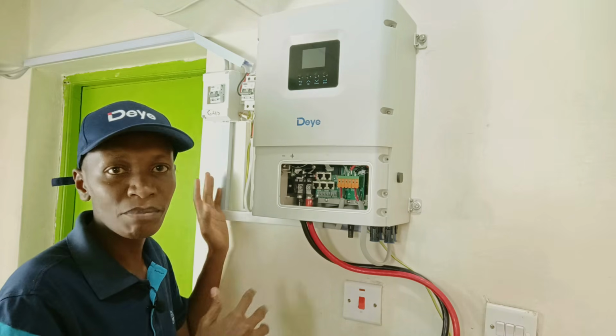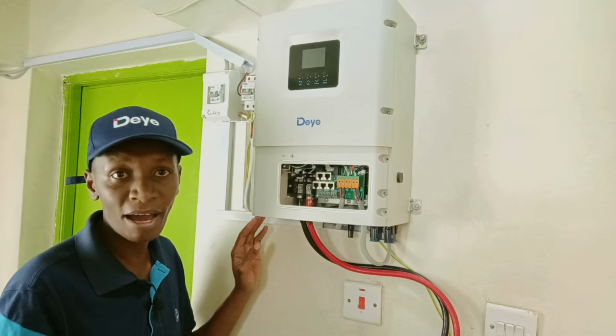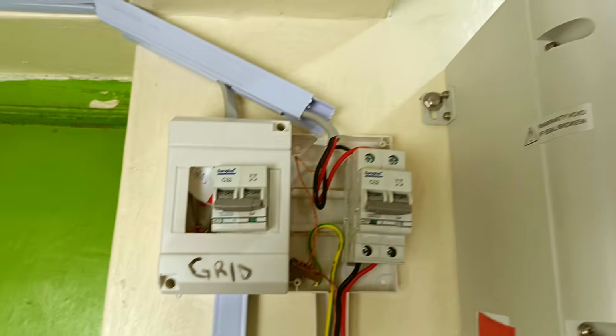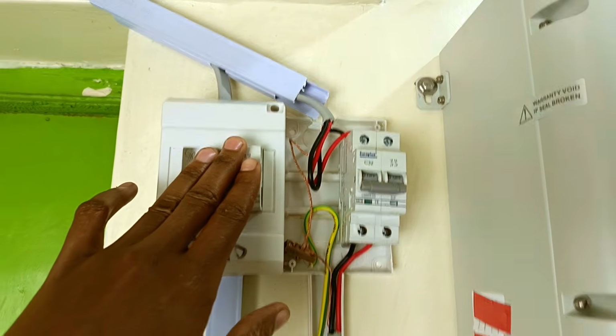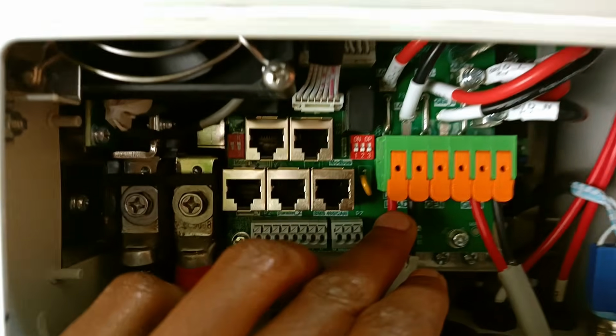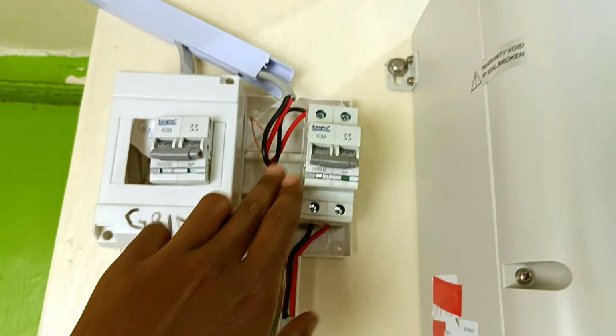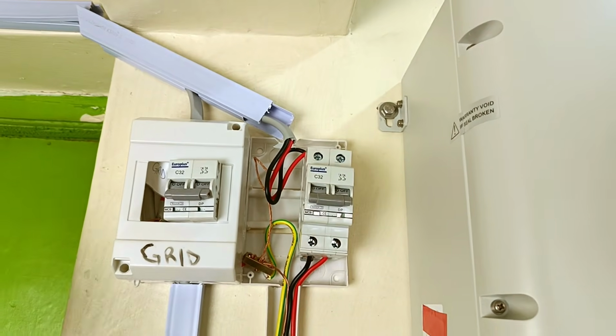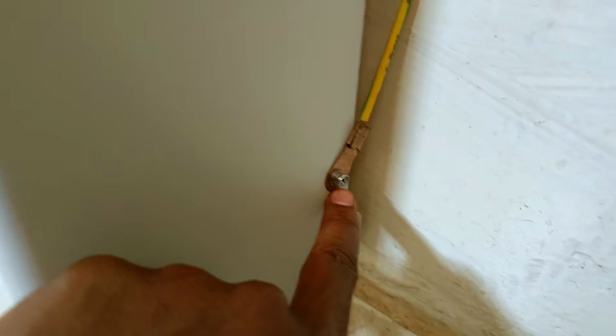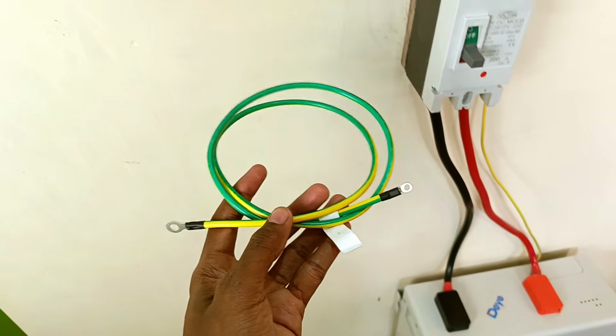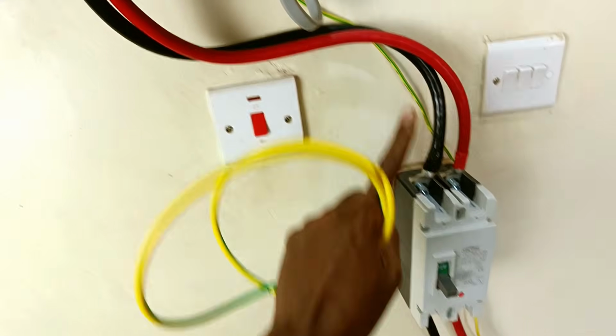I have already installed the AC breakers, DC breaker, as well as the protective earth cable. Let me just take you through my installation. Power from my grid comes through this AC breaker and it goes into the grid port of the inverter. The output, which is the load, also goes through this AC breaker and into my backup load. This is my protective earth cable. It's connected to the inverter and then goes all the way down to the battery. The provided earth cable was too short, so I had to make my own.